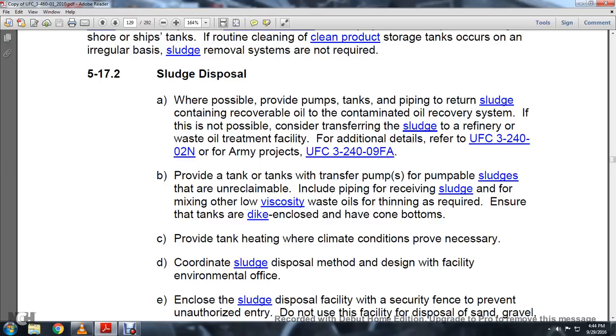5-17.2 Sludge disposal. When possible, provide pumps, tanks and pipes returning the sludge contained with the recoverable oil to the contaminated oil recovery system. If it is not possible, consider the transfer of the sludge to the refinery waste oil treatment facility. For additional details, refer to UFC 3-240-02N for Army projects, UFC 3-240-04N, and UFC 3-240-09FA.